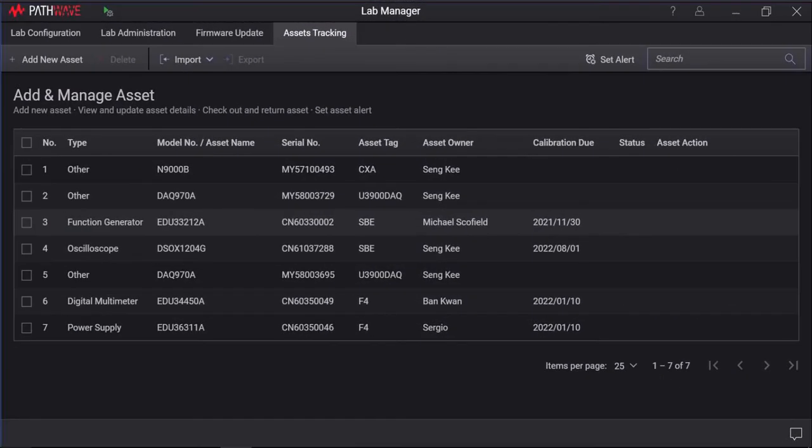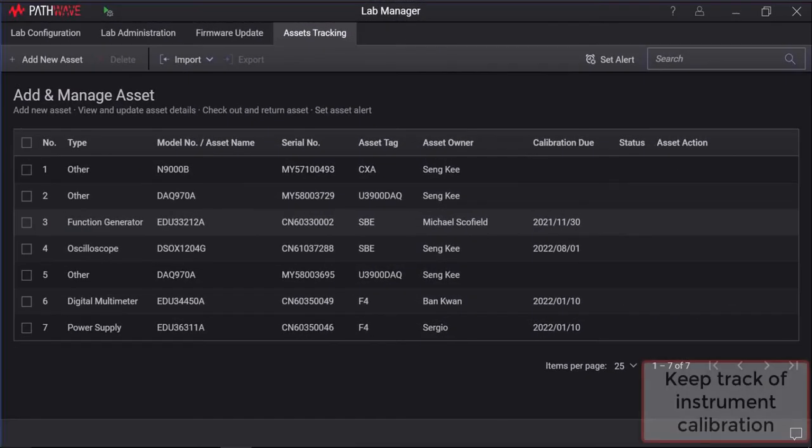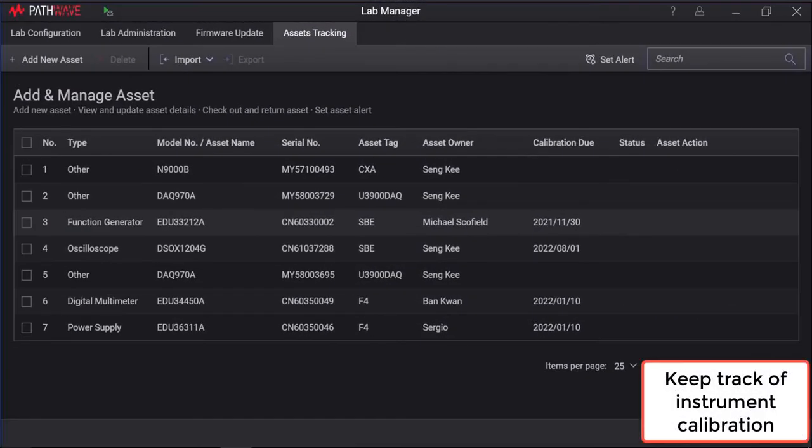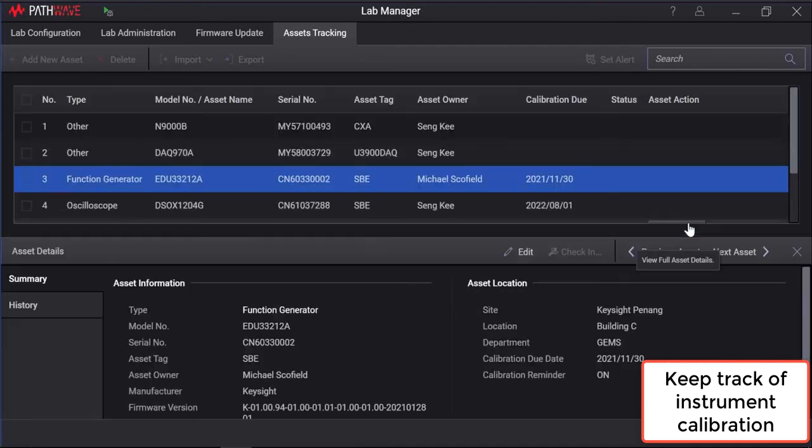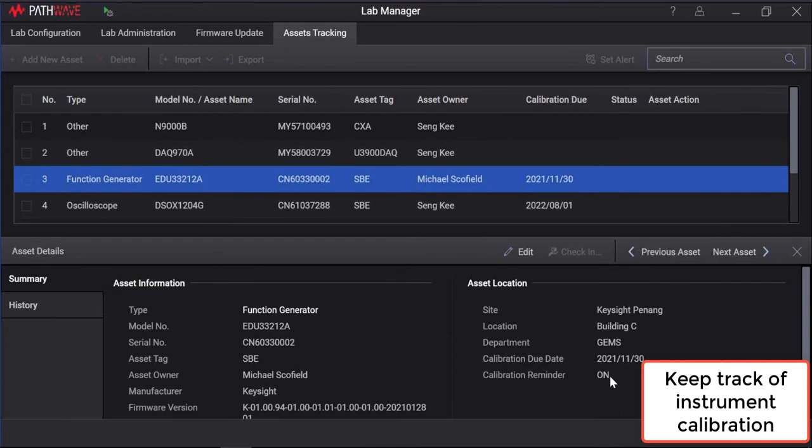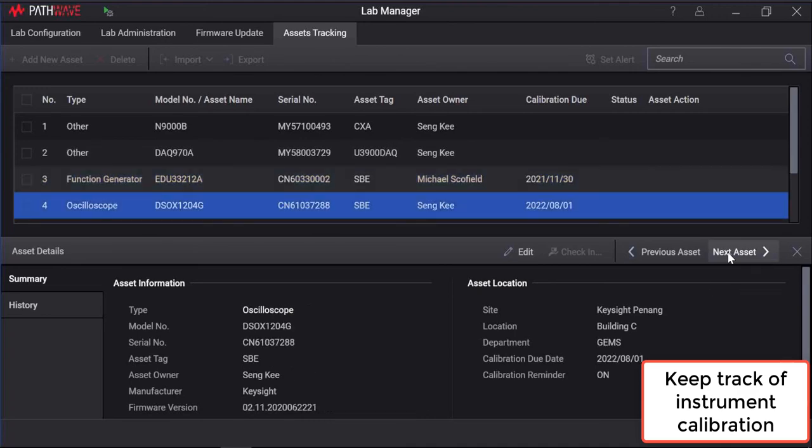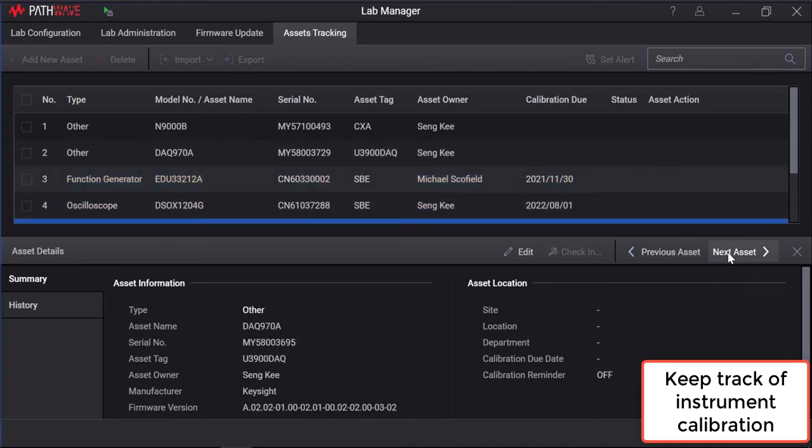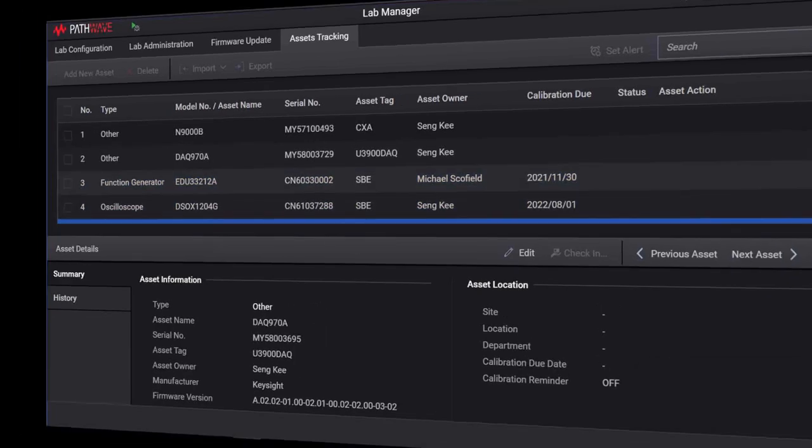PathWave Bench Vue Lab Manager include management tools to keep track of instrument's calibration. Calibration information can be added to each asset by selecting the desired asset and click the details button. The notification message will appear when the date is approaching on the actual date.